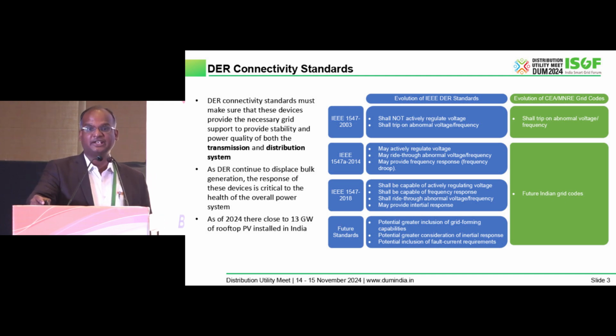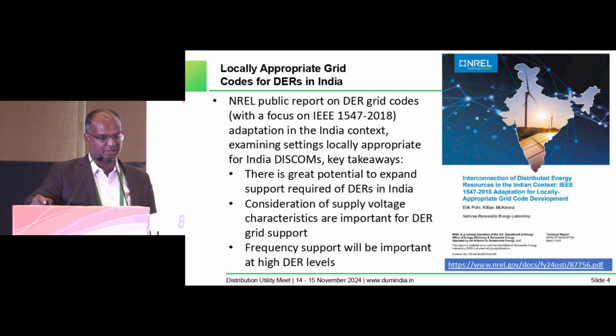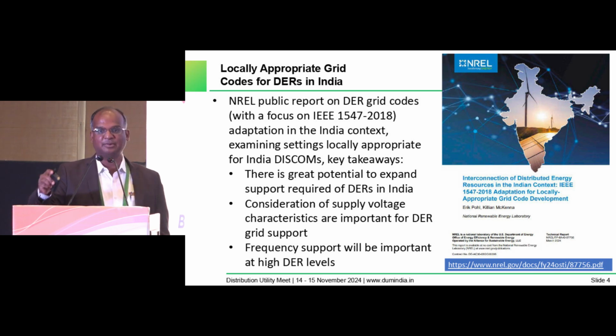I think 2018 took it to the next step, requiring capability for voltage regulation and frequency response, and also requiring ride-through — you don't have the option to just disconnect from the grid, that's not an option anymore. It should also provide voltage response if possible.